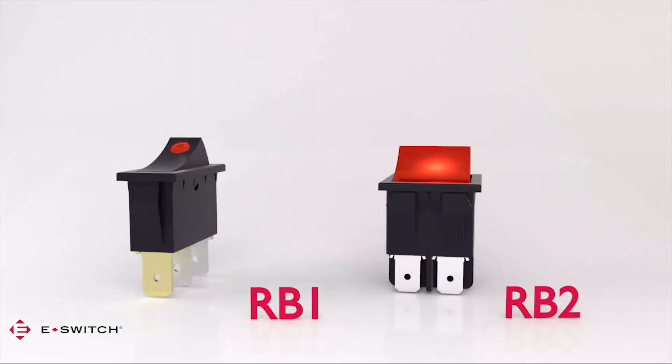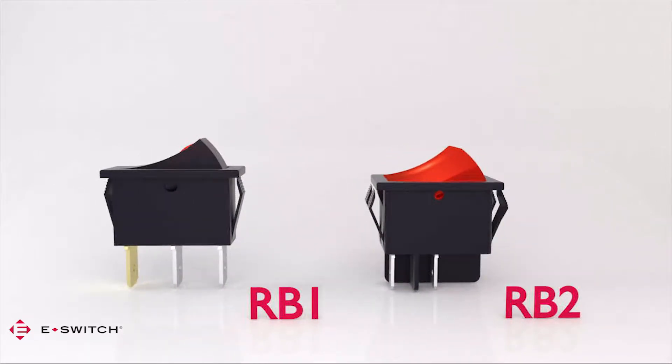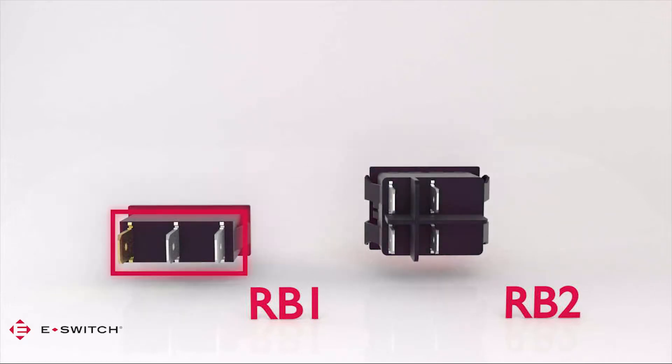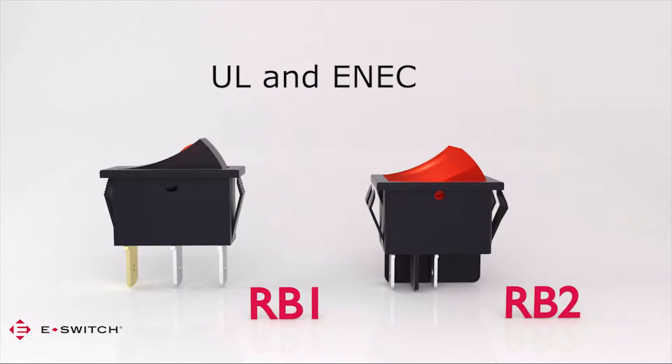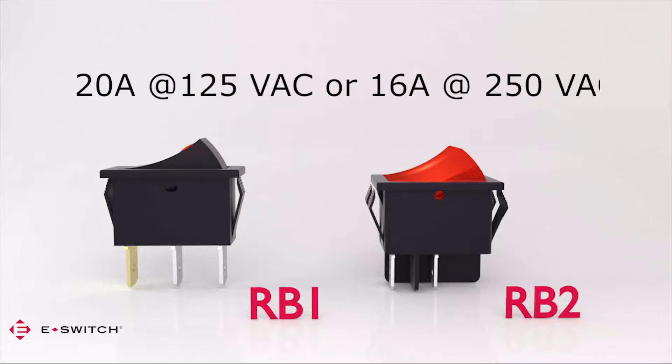The RB1 and RB2 are medium-sized rocker switches that fit into industry standard panel cutout sizes of 11 by 30 millimeters for the RB1 and 22 by 30 millimeters for the RB2. The RB1 is a single-pole switch and the RB2 is the double-pole version. Both carry safety listings from UL and ENEC and have contact ratings up to 20 amps at 125 volts AC or 16 amps at 250 volts AC.